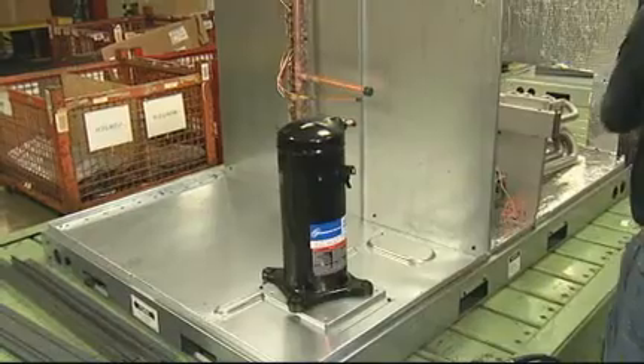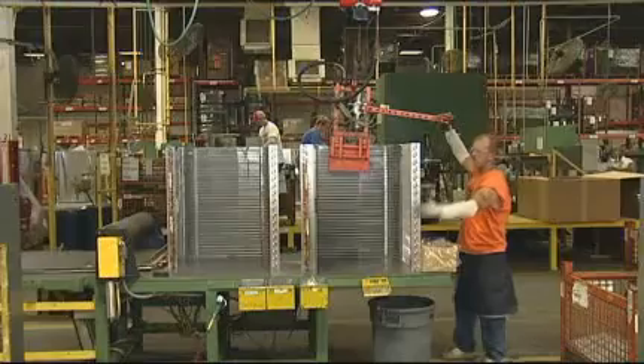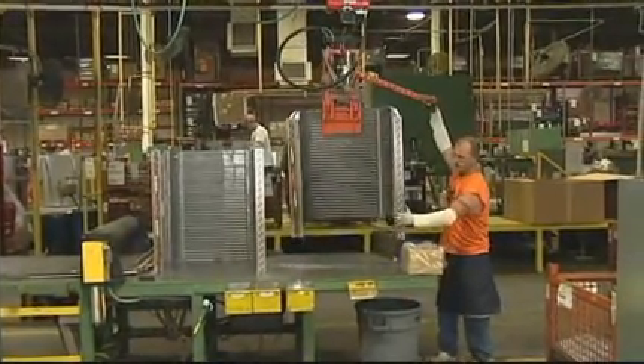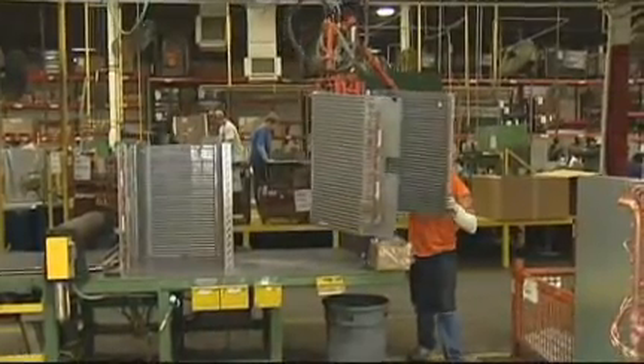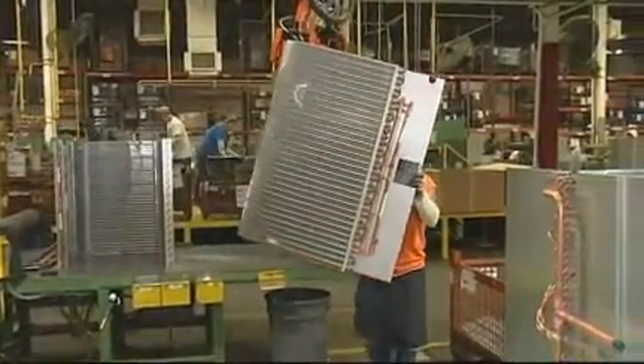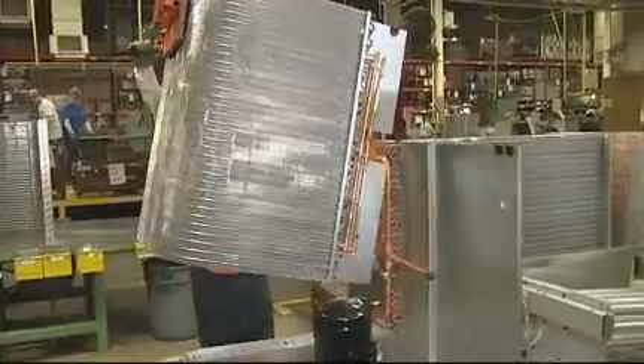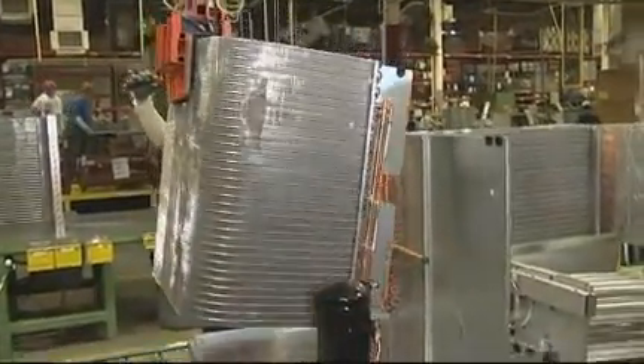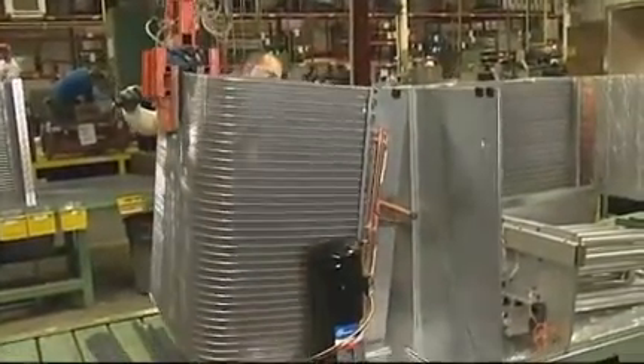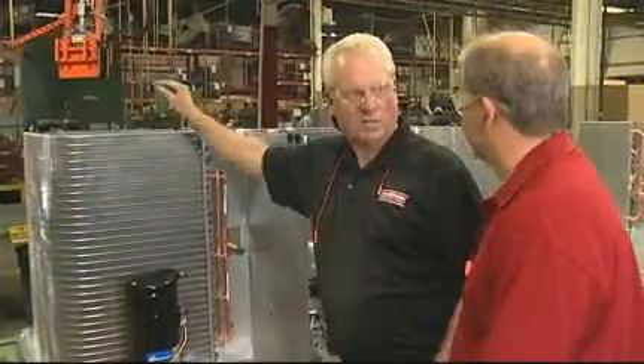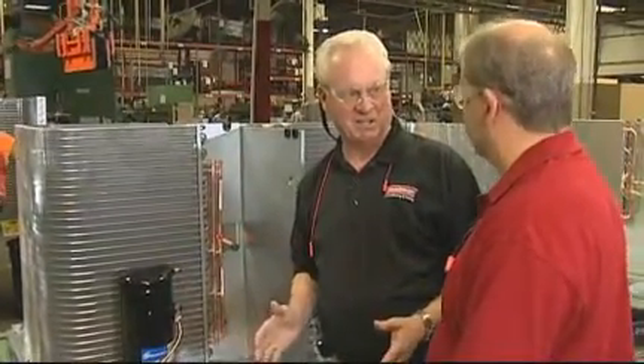As you can see, the evaporator coil is already installed, and the condenser coil, this operator across the line is using an assist device to bring the condenser coil over and set in the unit. The compressor is outside of the coil. Right. Some of the designs put the compressor inside the condenser coil, where it's extremely difficult to get to. You almost have to disassemble the whole thing. Right.